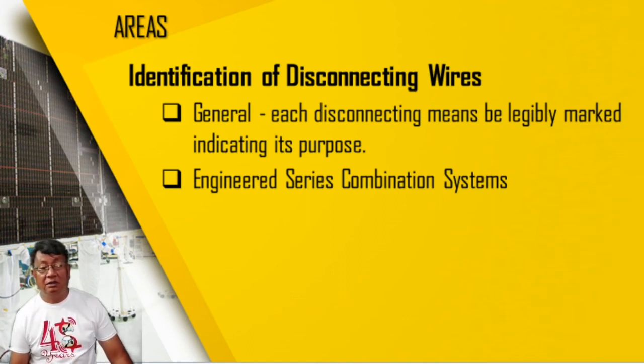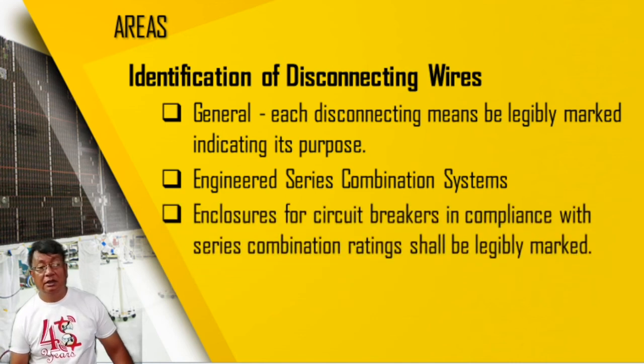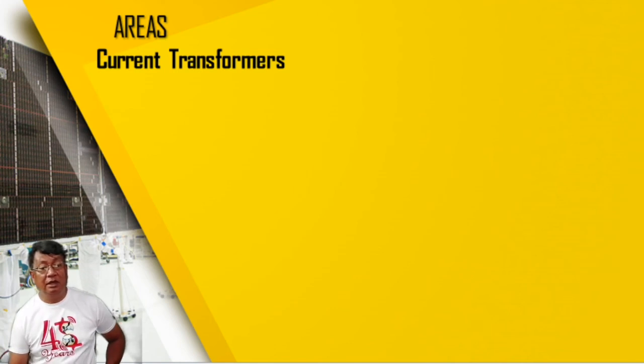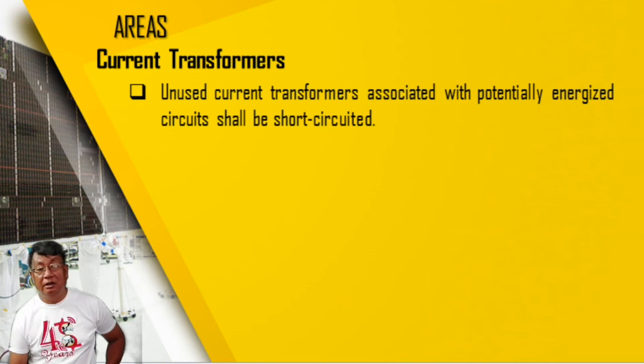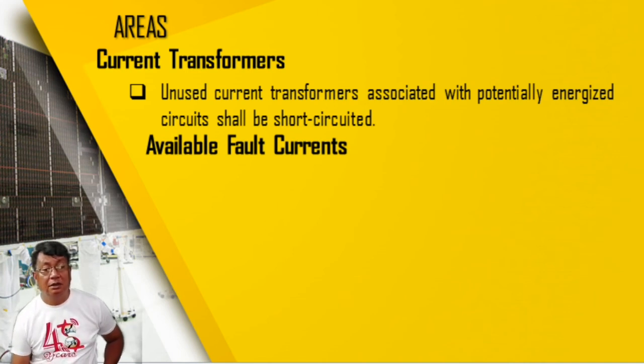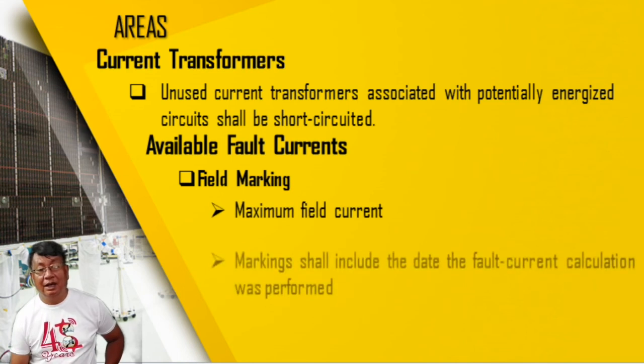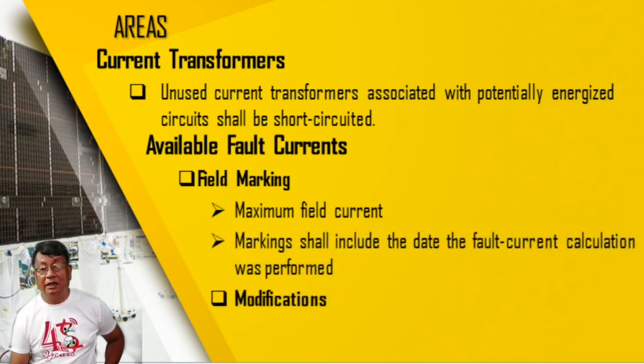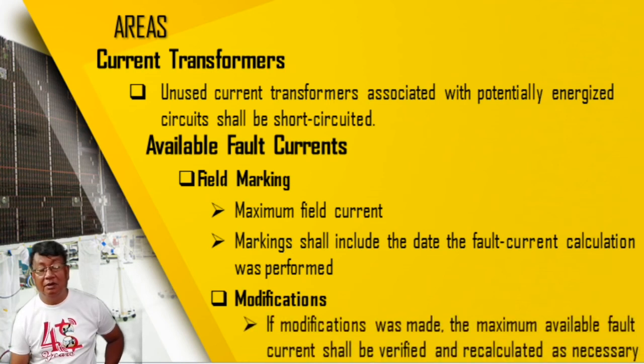Okay, engineered series combination systems. Enclosure for circuit breakers in compliance with series combination ratings shall be legibly marked. Current transformers. Okay, so unused current transformers associated with the potentially energized circuit shall be short-circuited. So that's very clear. Available fault currents. Okay, field markings. Maximum fault current marking shall include the date the fault current calculation was performed. So if a modification was made, the maximum available fault current shall be verified and recalculated as necessary.